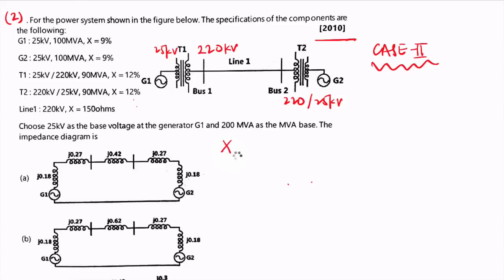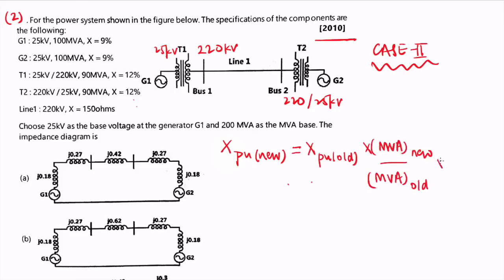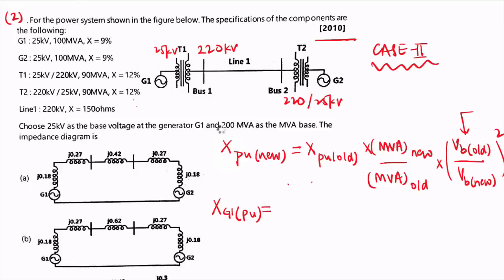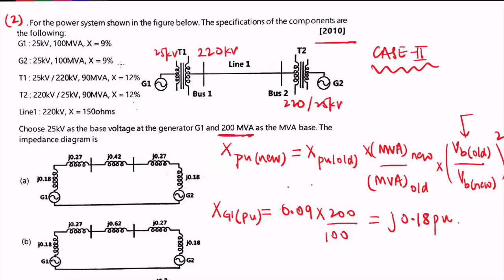Using the formula X_new (pu) = X_old (pu) × (MVA_new / MVA_old) × (V_base_old / V_base_new)², and since base voltages are the same the ratio is 1. So Xg1 (pu) at 200 MVA = 0.09 × (200 / 100) = j0.18 pu. G2 has the same parameters, so Xg2 = j0.18 pu as well.